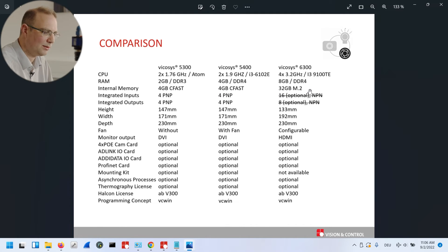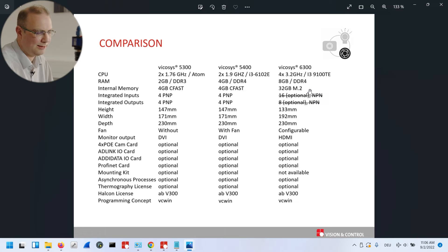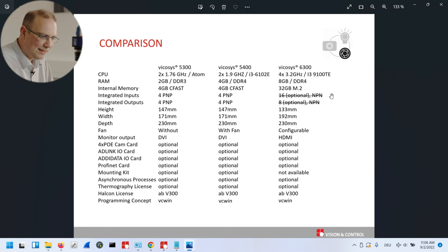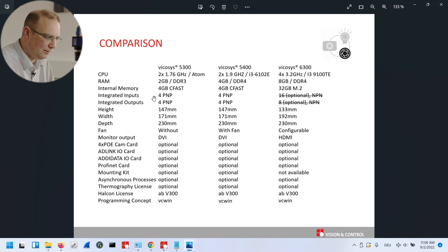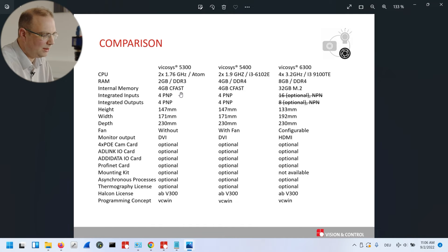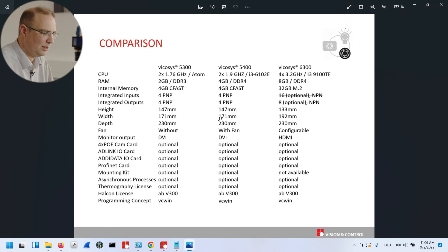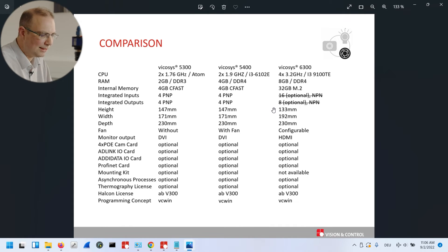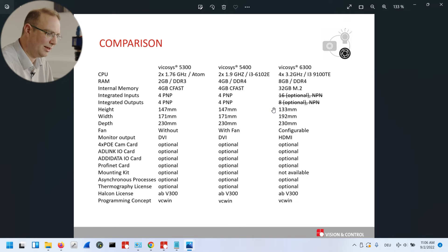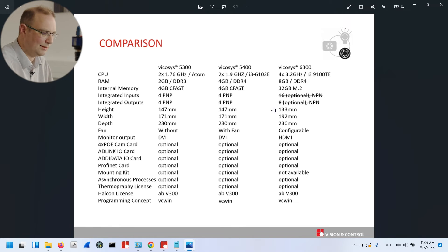And also the speed of this internal device increased significantly. An important difference is the, by default, assembled digital IOs. You see that the old systems had 4 inputs and 4 outputs. By default, the new system does not have that. You have to select in the product configurator one of the interface cards.